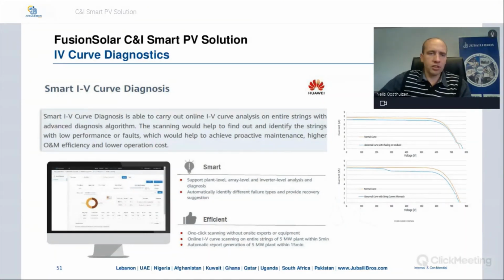Then continuing on the smart IV curve diagnosis, you can see on these graphs a typical graph would be the yellow one, the blue one would be what's picked up on the IV curve. The artificial intelligence will compare these two graphs and then specify what's the possible problem on the system. So it supports plant level, array level, and inverter level analysis and diagnosis, and it automatically identifies different failure types and provides recovery suggestions. So there's up to 16 different faults that can be identified by making use of the smart IV curve diagnosis.